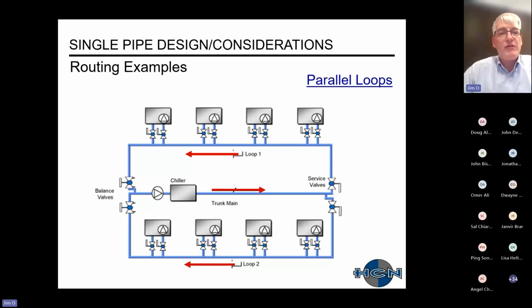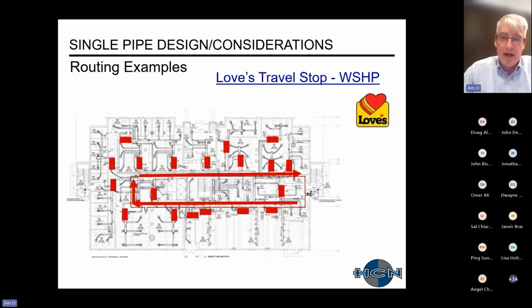Next couple slides are just showing a couple routing examples of single pipe systems. This one here, you have parallel loops. You have your supply coming out in the center, and then loop 1 going up to the top, loop 2 going to the bottom. This is an example of a Love's truck stop, or I should say travel stop, that has a water source heat pump system.